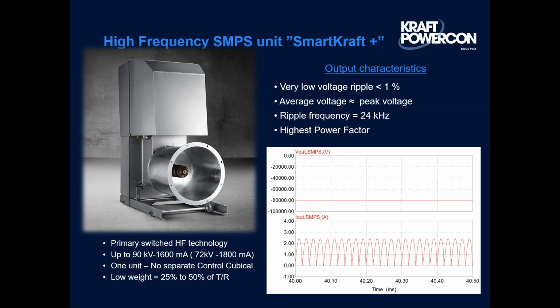If you move to the next slide, we have an SMPS. The SMPS has a true flatline DC, runs at a much higher frequency, and is a small compact unit. This has become very popular through the years because it's very inexpensive to install - it's one unit, goes up on the roof, smaller than even a single-phase TR set, and there's no separate control cabinet. There's been some reliability concerns over the years with SMPS technology, and how that technology is applied from other applications to a precipitator industrial application has been a challenge. I believe we've countered that, and I'll get into that further on in this presentation.